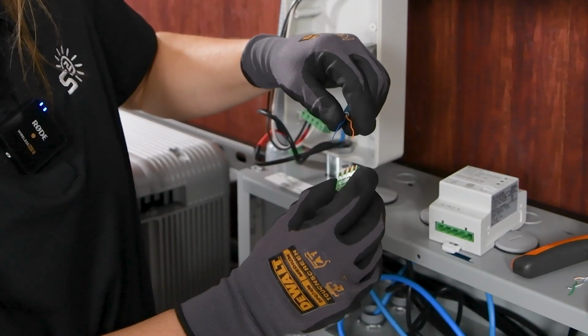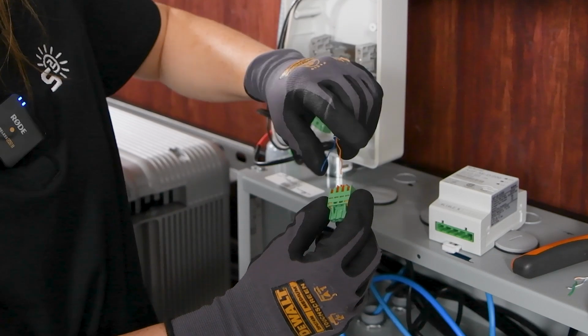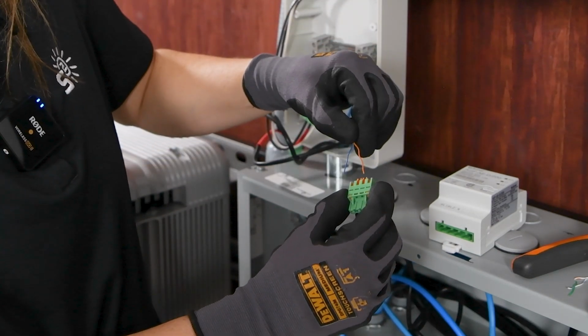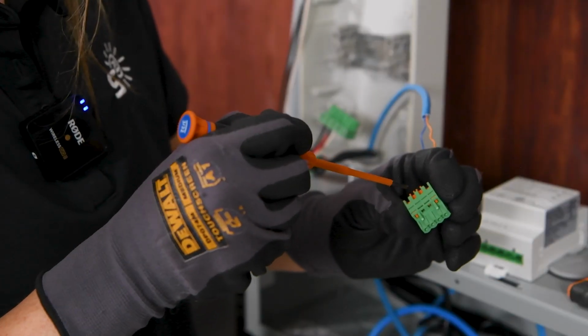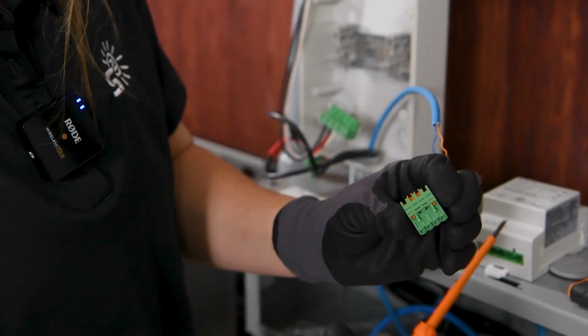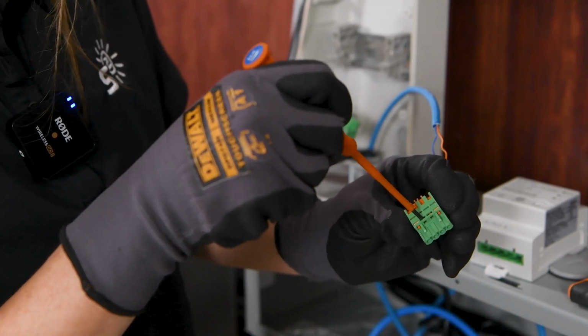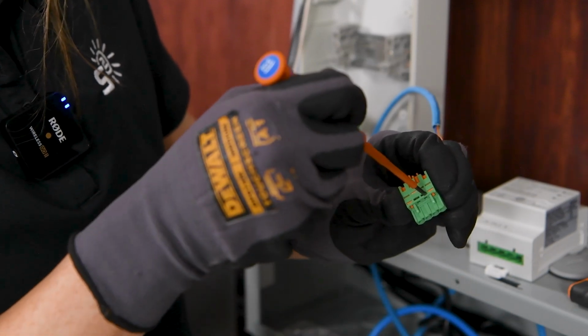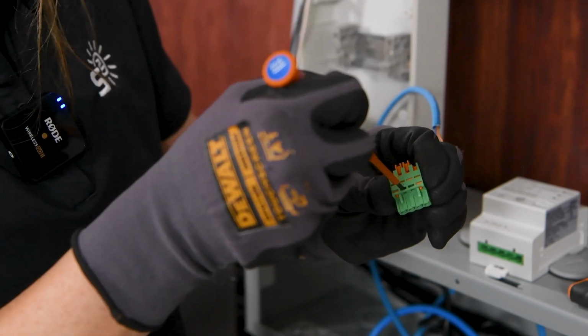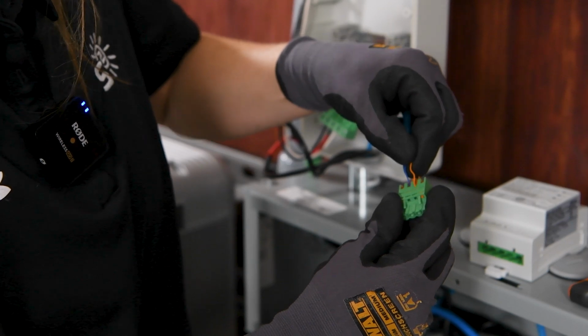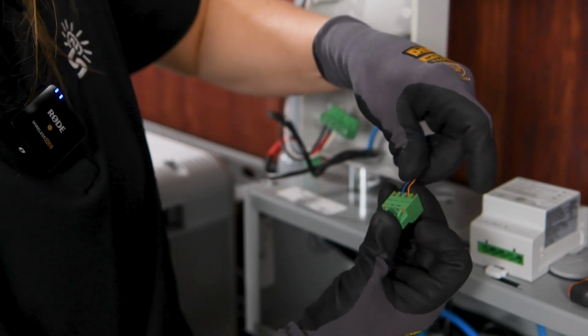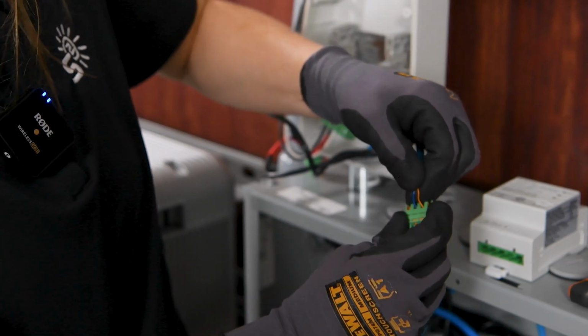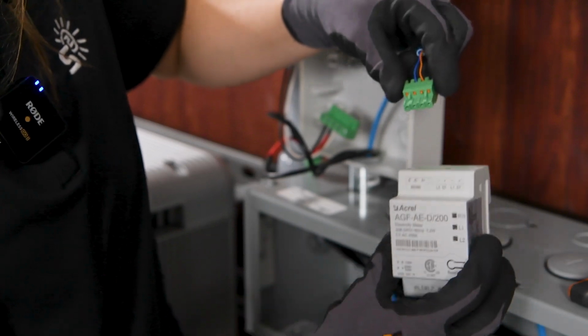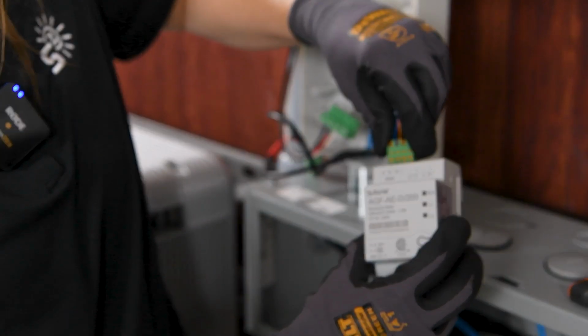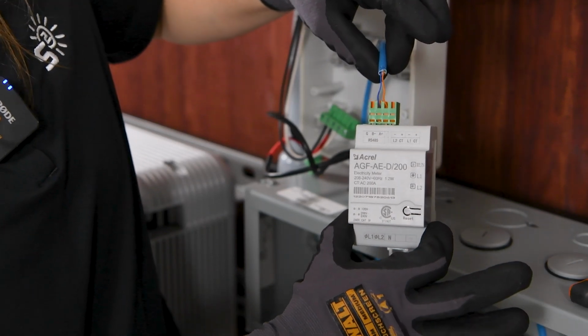As we look at the connector, we don't have to strip the wires as we insert them. They've got some blades in there that will strip the wire for you and make the connection themselves. You want to make sure that your orange clips are lifted up all the way, and to do that, you can use a small screwdriver and go into this bottom slit, insert it in, and just lift up. Make sure that those orange pins are lifted up as far as they can go. And that will open them wide, and then you can just snap them down into place and tug to make sure you get a good connection. Then you can slide this into your RS485 connection, and you've made communication with your Acrel meter.